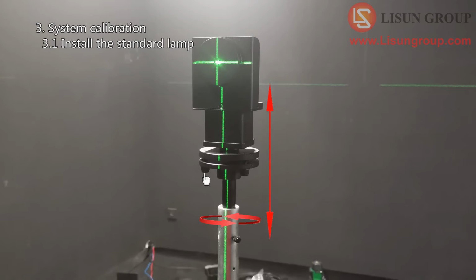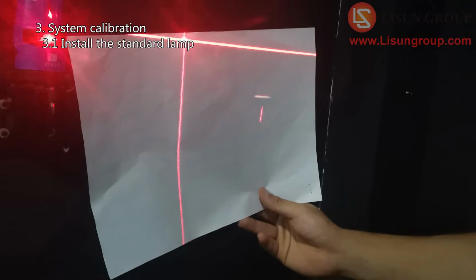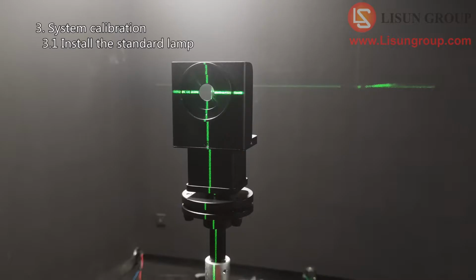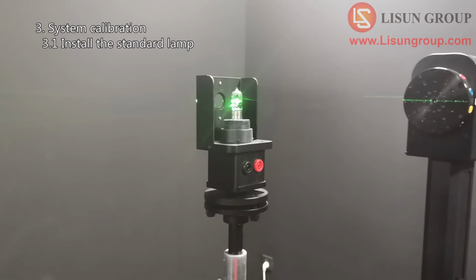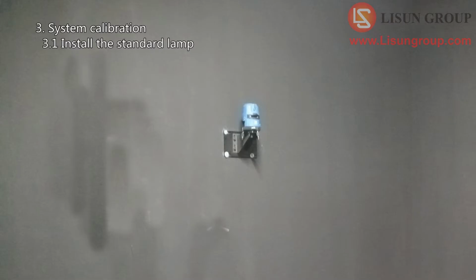Then need to adjust the height of the standard lamp, the direction of the standard lamp. Make sure that the cross laser hit the center of the mirror, and the reflected horizontal and vertical laser coincident with the original horizontal and vertical laser. Remove the mirror tool. Remove the cover of the standard lamp. Turn off the cross laser.